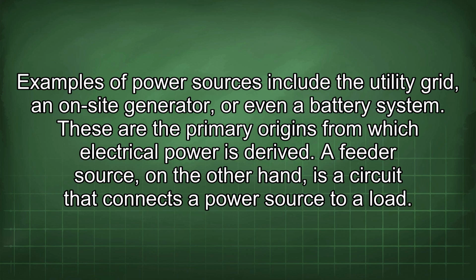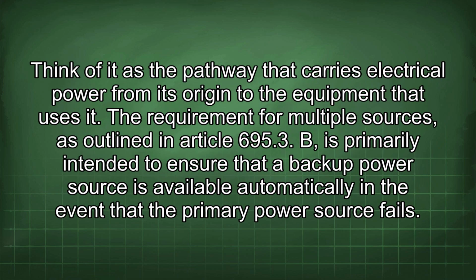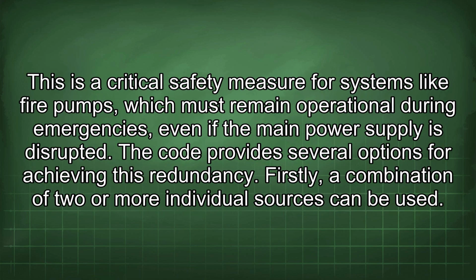A feeder source, on the other hand, is a circuit that connects a power source to a load. Think of it as the pathway that carries electrical power from its origin to the equipment that uses it. The requirement for multiple sources, as outlined in Article 695.3(B), is primarily intended to ensure that a backup power source is available automatically in the event that the primary power source fails. This is a critical safety measure for systems like fire pumps, which must remain operational during emergencies, even if the main power supply is disrupted.